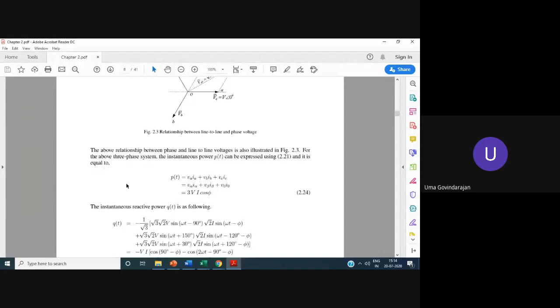The other components, oscillatory and reactive components, P oscillatory and Q, simply run between the source and the load, increasing the total volt ampere of the system, the total VA rating of the system. So in the three phase power factor definition, the numerator is always capital P average. This is the energy, whether it is an AC system or a DC system. The numerator is the work done component, the watt component. The denominator is the total VA, the three phase VA.